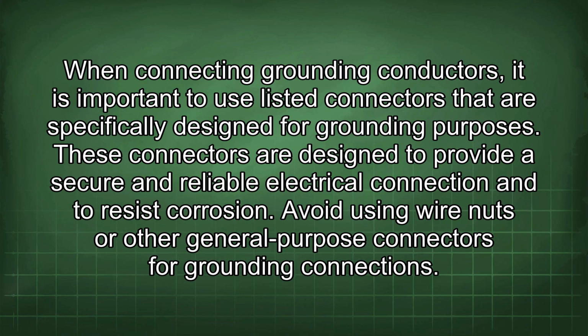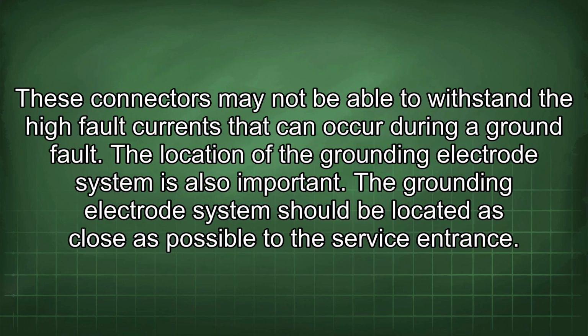contaminants. When connecting grounding conductors, it is important to use listed connectors that are specifically designed for grounding purposes. These connectors are designed to provide a secure and reliable electrical connection and to resist corrosion. Avoid using wire nuts or other general-purpose connectors for grounding connections. These connectors may not be able to withstand the high fault currents that could occur during a ground fault.